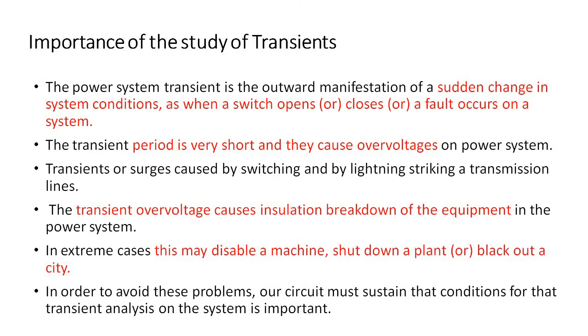Importance of the study of transients. Power system transients are the outward manifestation of a sudden change in system conditions, as when a switch opens or closes or a fault occurs on a system. The transient period is very short and they cause overvoltages on the power system. Transients are surges caused by switching and by lightning striking transmission lines. The transient overvoltages cause insulation breakdown of the equipment in the power system. In extreme cases, this may disable a machine, shut down a plant, or black out a city. In order to avoid this problem, our circuit must sustain that condition, so transient analysis of the system is important.